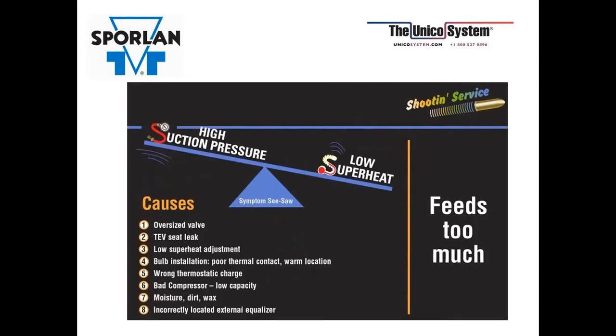Next one is feeds too much. You're going to have high suction pressure because you're not boiling off that refrigerant, and you're going to have low superheat because you're not boiling it off. There's not enough time for it to gain enough superheat. And that could be an oversized valve. It could be a seat leakage issue. But if you look down at number 7, there you go, moisture, dirt, wax. So it's blamed for a lot of stuff.